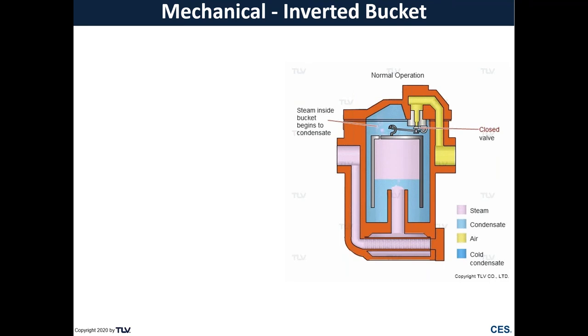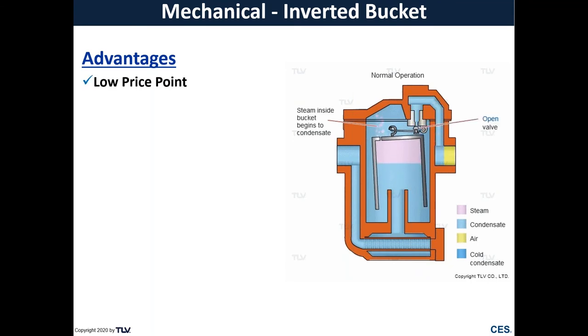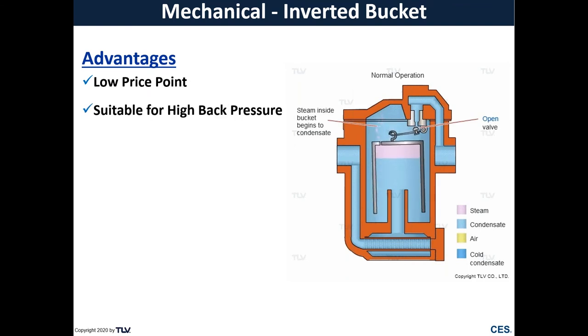bucket already. So some advantages to this model: depending on your material and connection size, this can be a relatively inexpensive steam trap. It's suitable for high back pressures. So mechanical steam traps in general can handle a high back pressure as long as you maintain some sort of pressure differential.